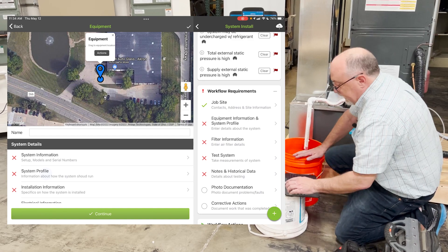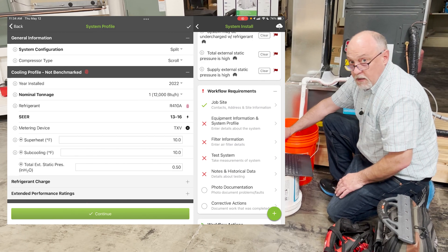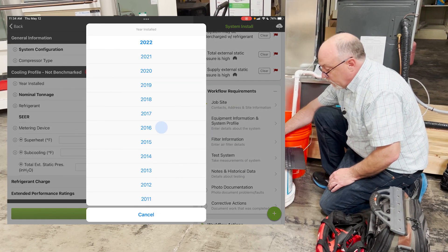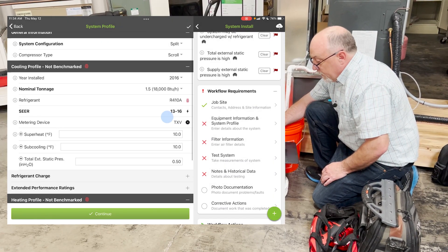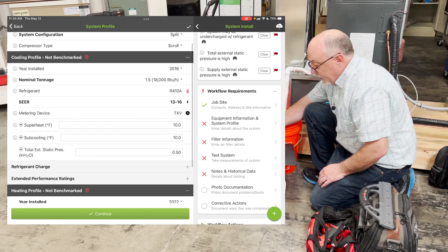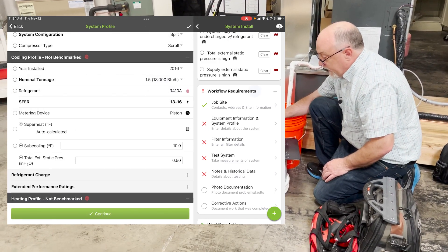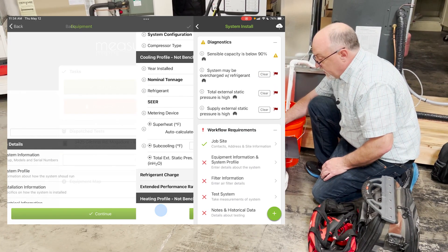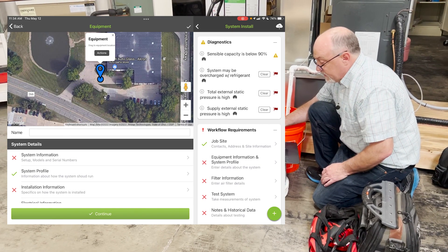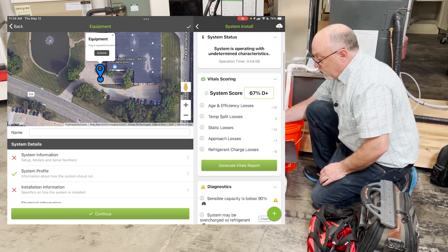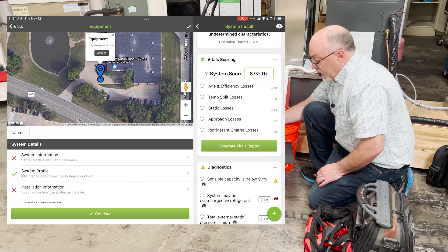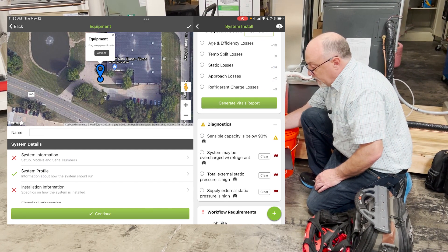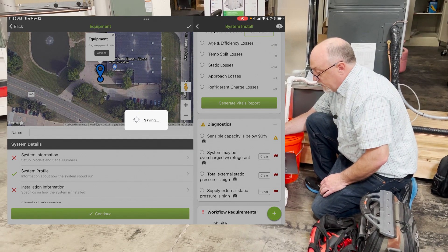Equipment profile is the next piece — it's important to put in here because we need to know what kind of system it is. Let's say this is a 2016 piece of equipment and it's a ton and a half. That's going to feed into our algorithms that calculate age and efficiency losses. In this case, we have a piston, and that's going to affect our diagnostics. You can see right here it says TXV may be loose — as soon as I hit continue, that fault is going to go away because now we know it's not a TXV system, and it's going to rescore. Now we have a score running about a D-plus, with losses due to age and initial efficiency, no temp split losses, static pressure losses of 14, approach losses of 2, and refrigerant charge losses of 8.